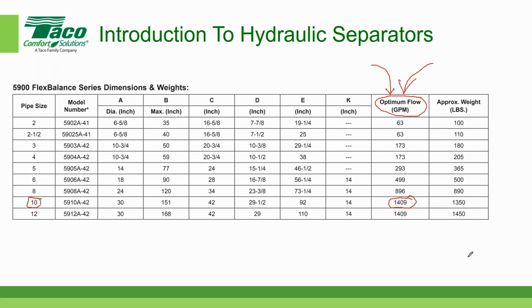There's no other calculation that you can do. You have to come to this table, look at the optimum flow for your system and then select the size. So let's assume for a moment we had 550 gallons per minute. At first you might say, well, 550, that would be good for a 6-inch. But in fact, for 550, you'd have to go to the next size, an 8-inch, for that to work.